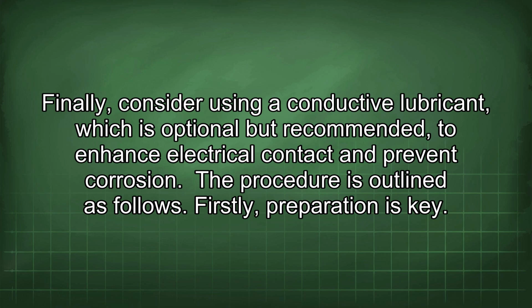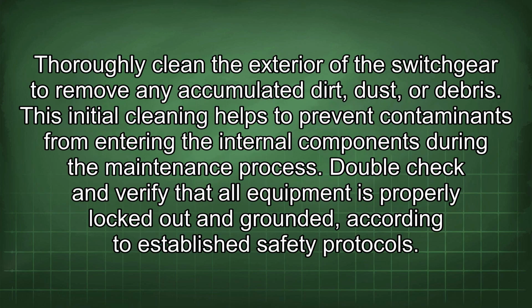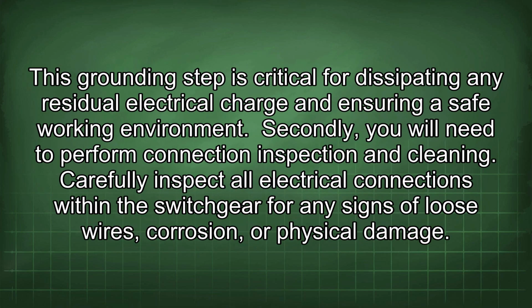Firstly, preparation is key. Thoroughly clean the exterior of the switchgear to remove any accumulated dirt, dust, or debris. This initial cleaning helps to prevent contaminants from entering the internal components during the maintenance process. Double-check and verify that all equipment is properly locked out and grounded, according to established safety protocols. This grounding step is critical for dissipating any residual electrical charge and ensuring a safe working environment.